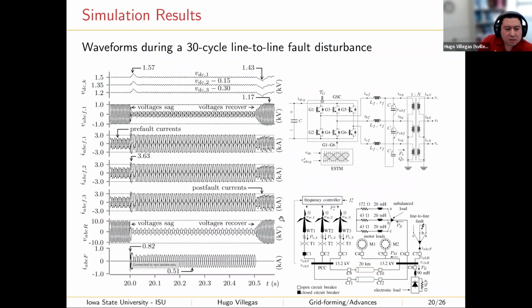But what is important is to observe the waveforms when we are studying the faults. Here I'm showing the pre-disturbance waveforms, the waveforms during the disturbance, and after the disturbance. During the pre-disturbance part, I'm showing the currents of the 3 wind turbines. If you can see here, the currents are unbalanced previous to the fault, and that has to happen because I'm applying an unbalanced load. You can see here the switchings. Also, the converters are switching at 3 kilohertz.